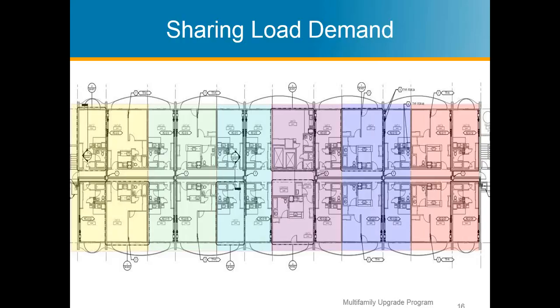Another example would be if you're in an office space and you have your perimeter open office areas on the outside by the windows, and then you have your interior core office cubicles, and they're able to work with each other to share that load and keep everybody satisfied. So every indoor unit has a thermostat, that's their control mechanism to run, or to go to heating or cooling mode. So you've got one control for every indoor unit that shares one outdoor unit. It's a really great system, and the mentality and the thought of it is great.